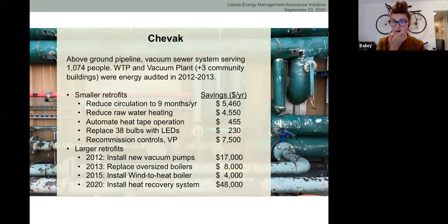And so that work included reducing circulation to 9 months per year. So running those pumps that circulate water in the distribution loops only during that heating season, because before they were running all year round, and that wasn't necessary. And that was using electricity that didn't need to be used. Reduce raw water heating. So again, like dialing in that temperature to which water is heated and not heating it more than it needs to be to prevent freezing. Automate heat tape operations. So heat tapes are only operating when water is stagnant in a pipeline or when certain temperatures are reached. Replacing LEDs in the treatment plant and vacuum plant, and recommissioning controls. And then there's examples of annual savings for making these different changes.